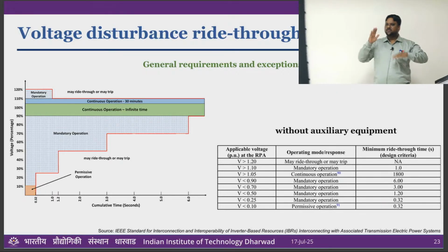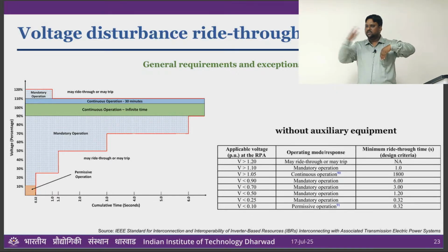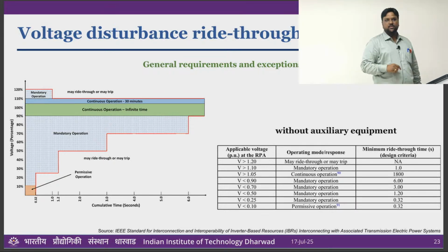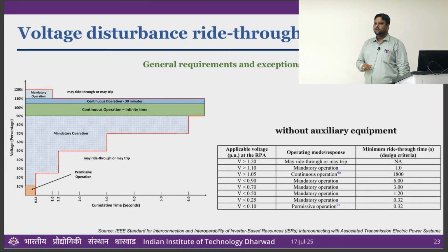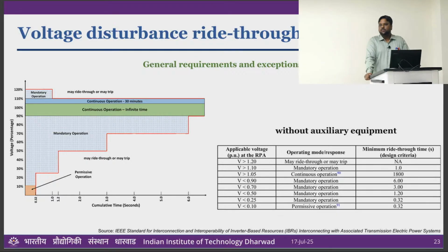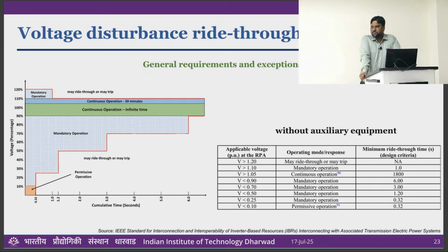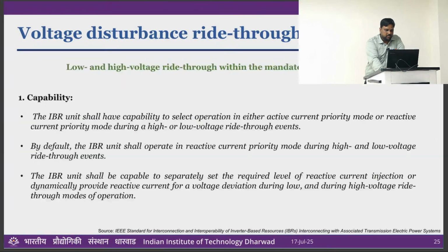So that misunderstanding between the IBR unit and the plant causes some oscillations in the reactive power, which the Rajasthan grid is now facing due to the renewable solar power plant integrations. So now they are looking at how to estimate the exact voltage drop at the terminal, because this is not terminal voltage, this is POI voltage. Okay, so research is going on that.